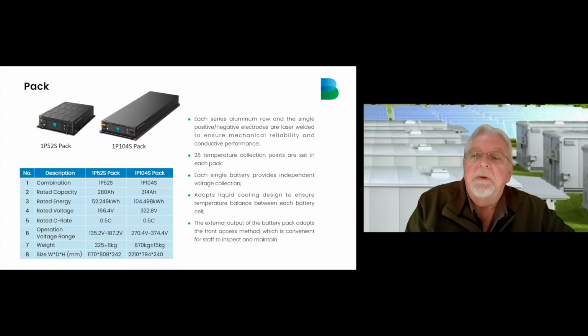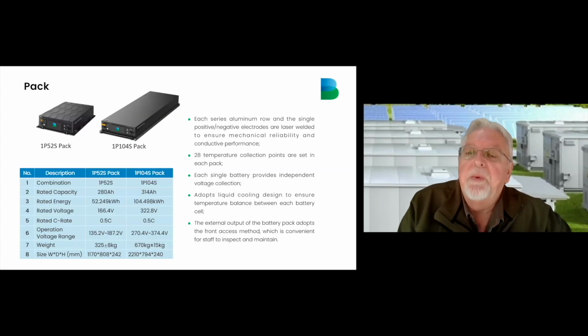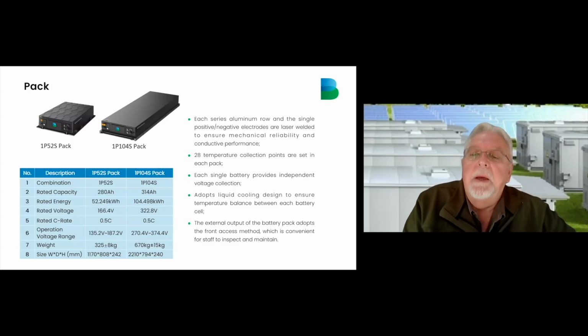On the top left, you've got a 52 cell battery pack. It is used in a 0.5C 3 megawatt hour BES container, and the 104 cell battery pack is used in a 0.25 and a 0.5C 5 megawatt hour BES container. It is very important to note the weight of these liquid cooled batteries, which may vary between 310 kilograms and up to 685 kilograms per battery pack. So for on-site maintenance purposes, you will need to use a forklift to replace a battery if needed.